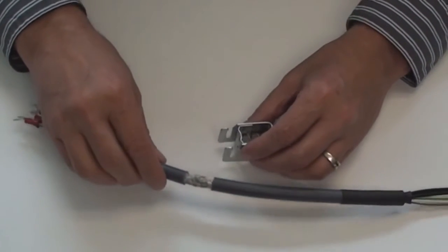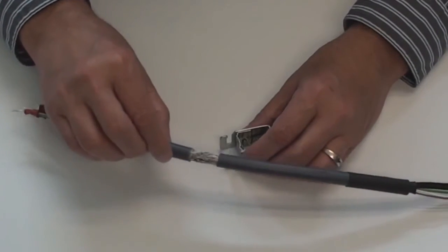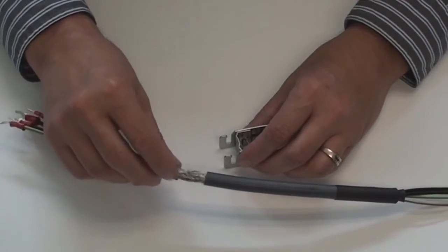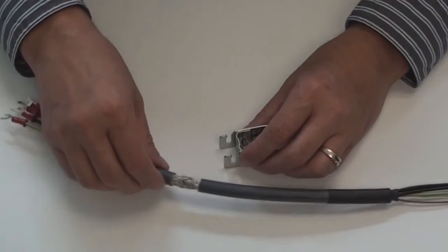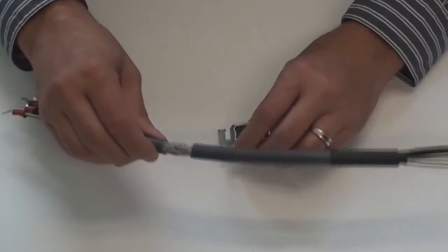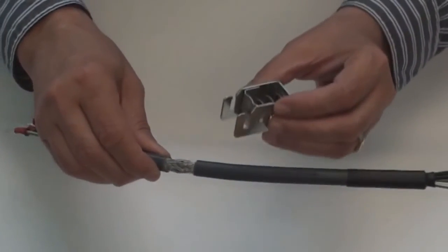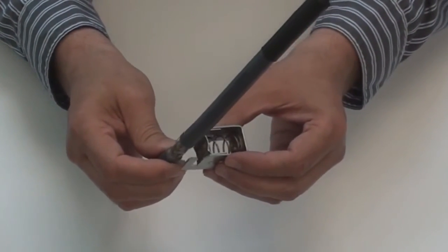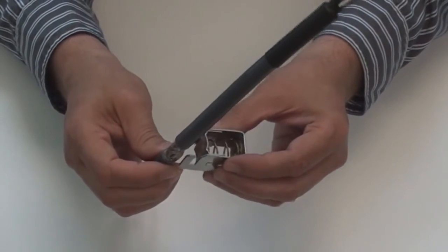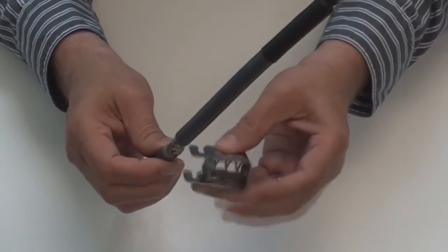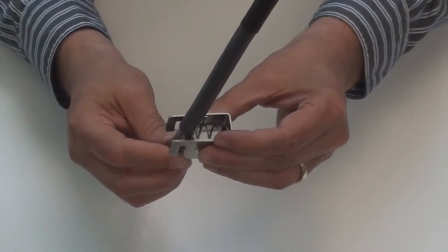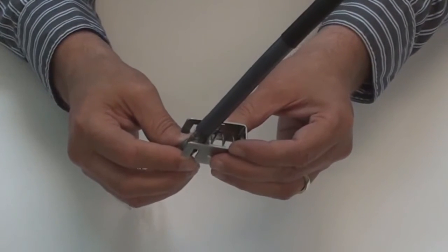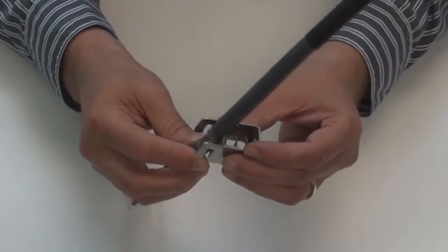Okay, now I'm going to show you how to cut this power cable and expose the shield. And as you can see, I've done that with about two inches of space. We're going to take this shield and connect it to what we call a saddle clamp, which has a 360 degree coverage. What we want to do is attach this to the machine's ground by attaching this clamp to the machine's back plane, the panel, so that both the ground of the cable shield and the machine itself are at the same ground point.